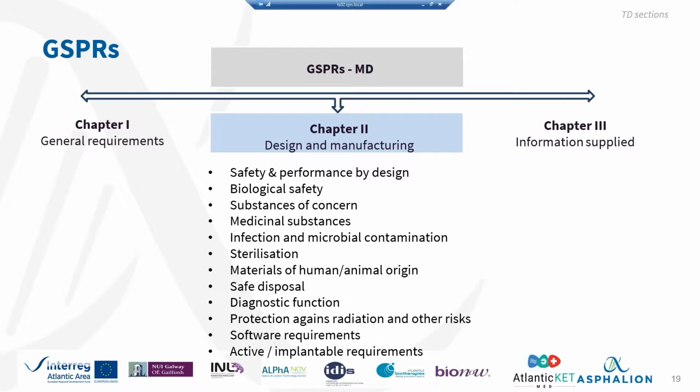If it has a diagnostic function, there will be specific requirements you will have to comply with, and you will also have to demonstrate that it's protected against radiation and other risks, environmental risks more than anything, such as heat and vibrations. Everything has to be addressed here. Obviously, if your device has software, you will have to fulfill the software requirements. And also you will have to provide information regarding active or implantable requirements. Okay, there are specific requirements for active and implantable devices.